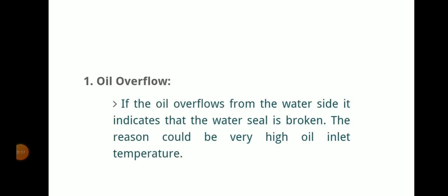Oil overflow means if the oil overflows from the water side, it indicates the water seal is broken. The reason could be very high oil inlet temperature.